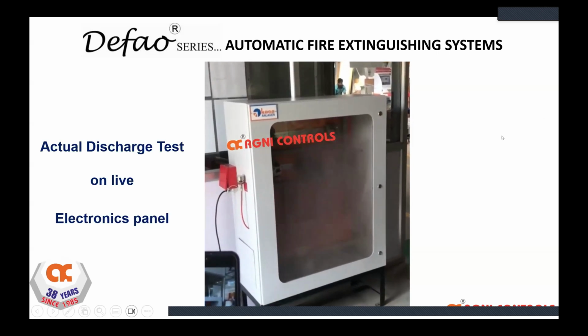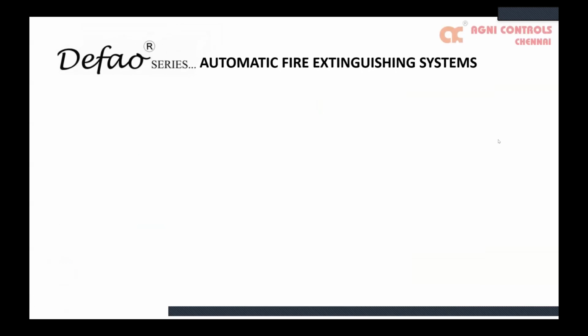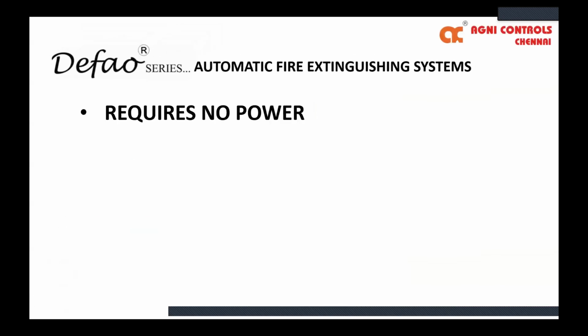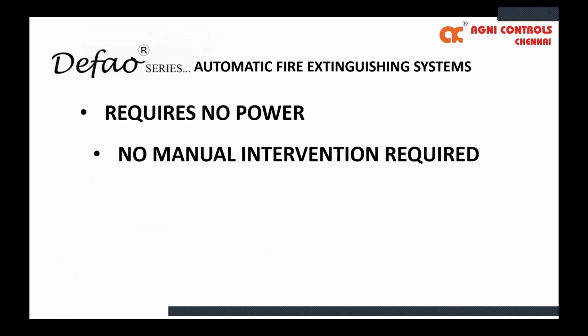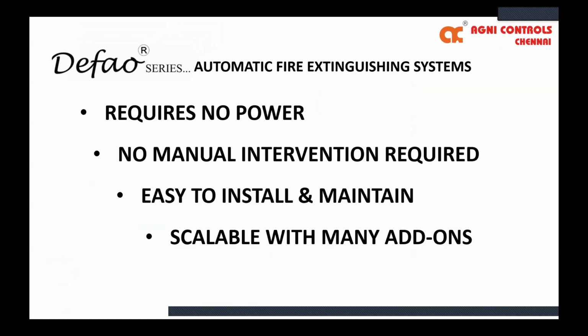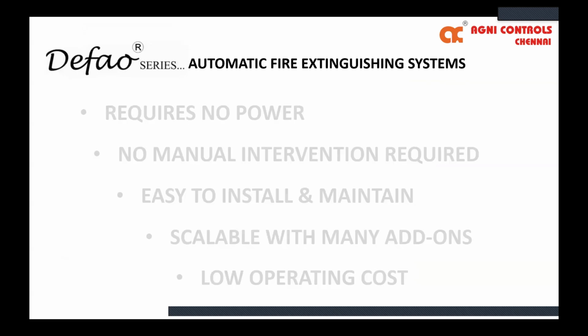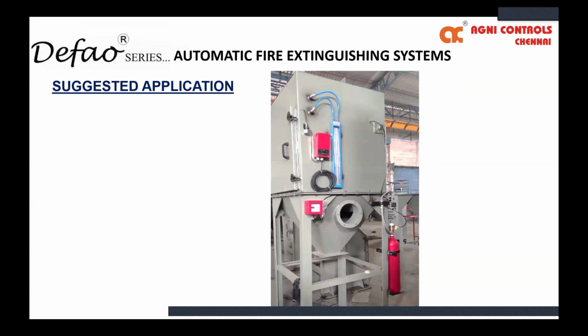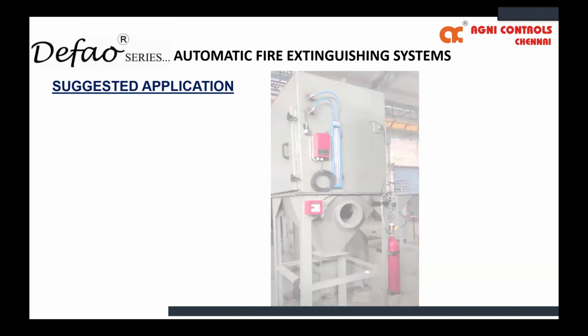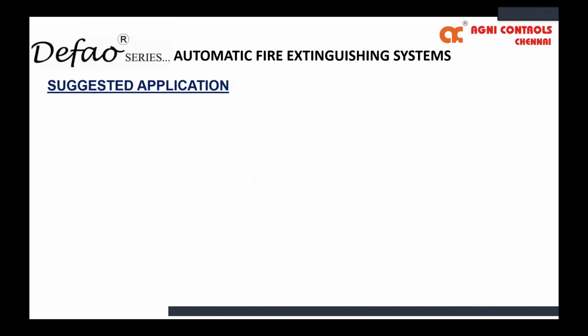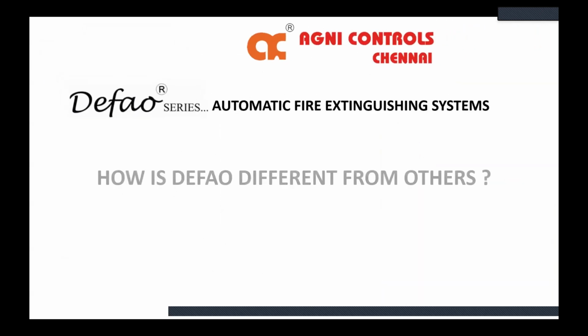This is the basic system of an automatic fire extinguishing system. So what is the benefit? It requires no power. Of course, if you want a hooter, you need the power supply, but in terms of the actual detection, you don't require power. It requires no manual intervention, is easy to install and maintain, scalable with many add-ons, and has low operating cost. These are all different applications where the automatic tubing systems are installed: electrical panels, battery racks, storage walls, etc.